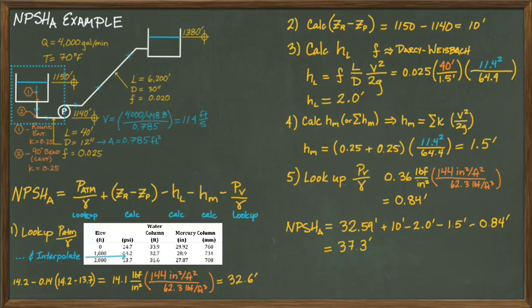As a final note, unless you end up as a water resources engineer, you may never do this calculation again. However, for all engineers, you need to understand what drives the problem of cavitation. There are two general causes. The first is not enough net positive suction head available, and the second is too much net positive suction head required by the pump. If you know each of the terms in the net positive suction head available calculation, then you should easily be able to understand the impact of changing any one of those values while keeping the others constant.